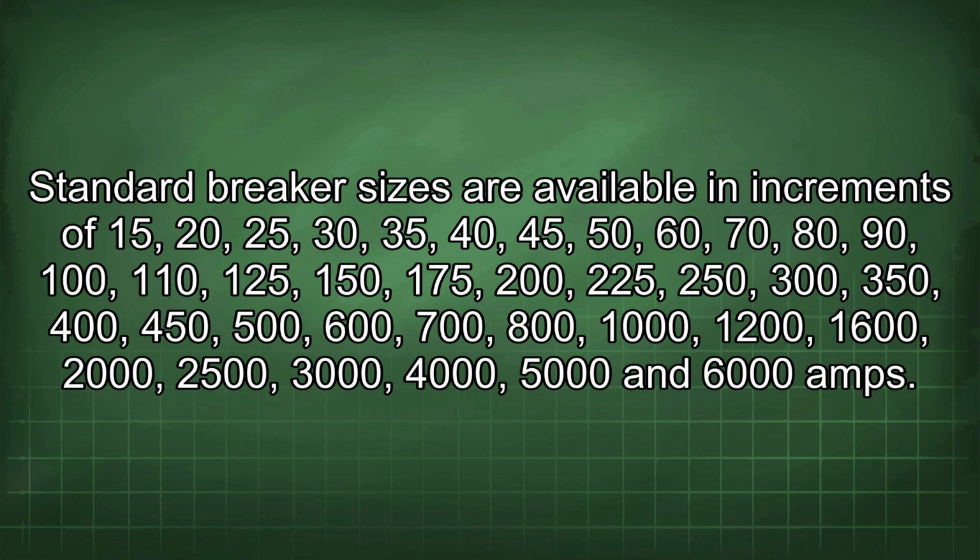Standard breaker sizes are available in increments of 15, 20, 25, 30, 35, 40, 45, 50, 60, 70, 80, 90, 100, 110, 125, 150, 175, 200, 225, 250, 300, 350, 400, 450, 500, 600, 700, 800, 1000, 1200, 1600, 2000, 2500, 3000, 4000, 5000, and 6000 amps.